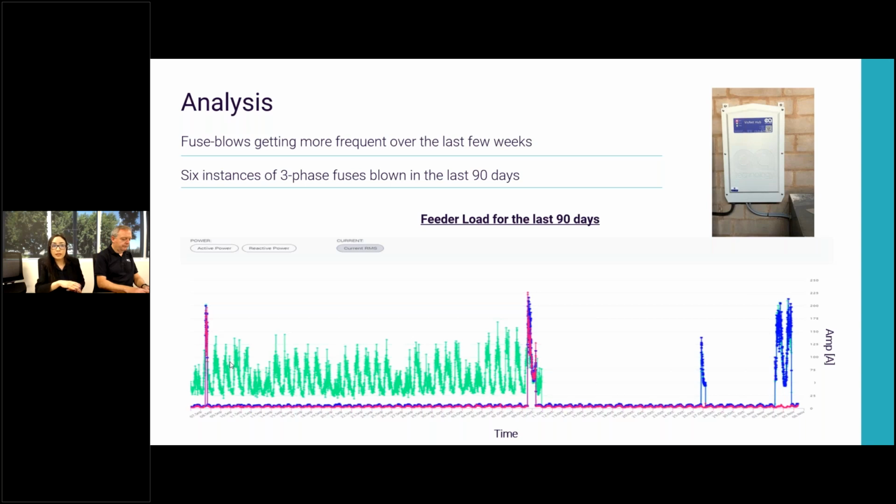At this point, they knew it. We were able to provide them with the power fault location, following exactly the same approach that you just explained. However, because they were short in staff and had a couple of other issues going on, they decided not to go and look at the fault location. So things kept going like normal when we lost two phases at that point.